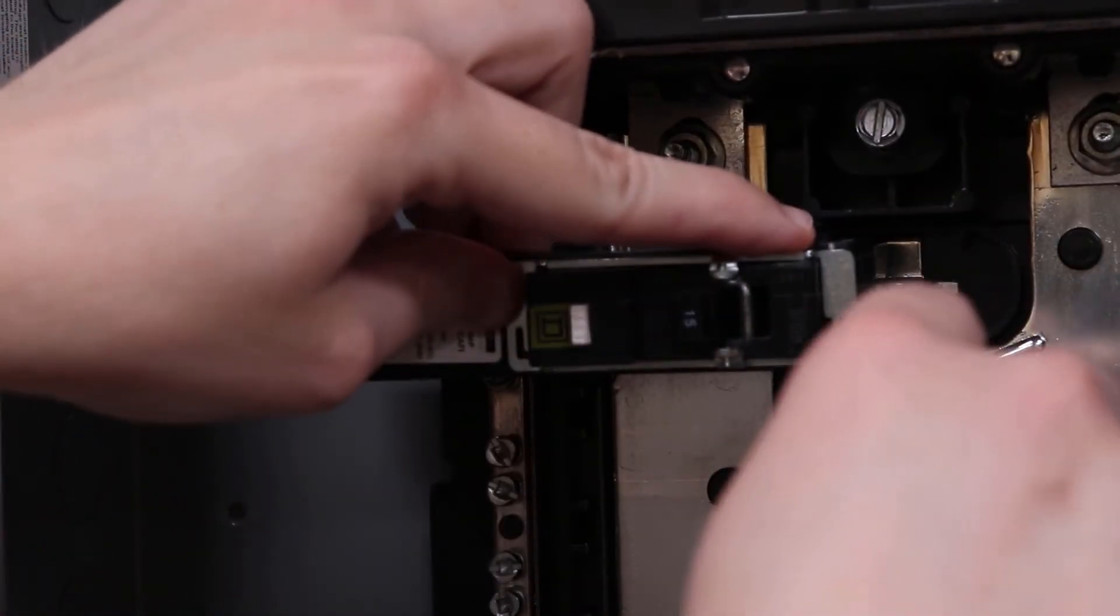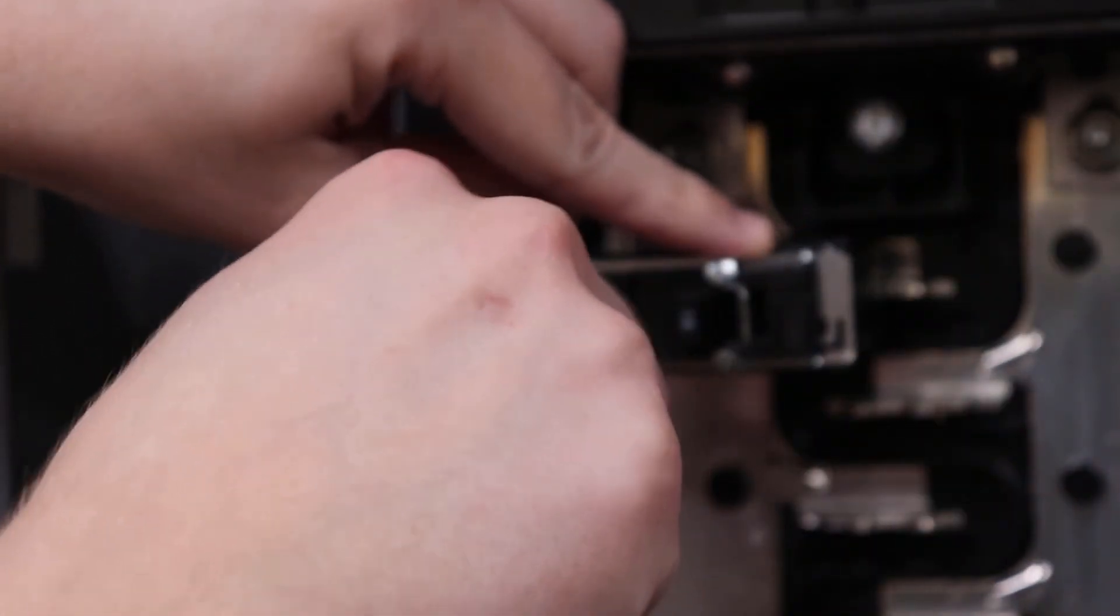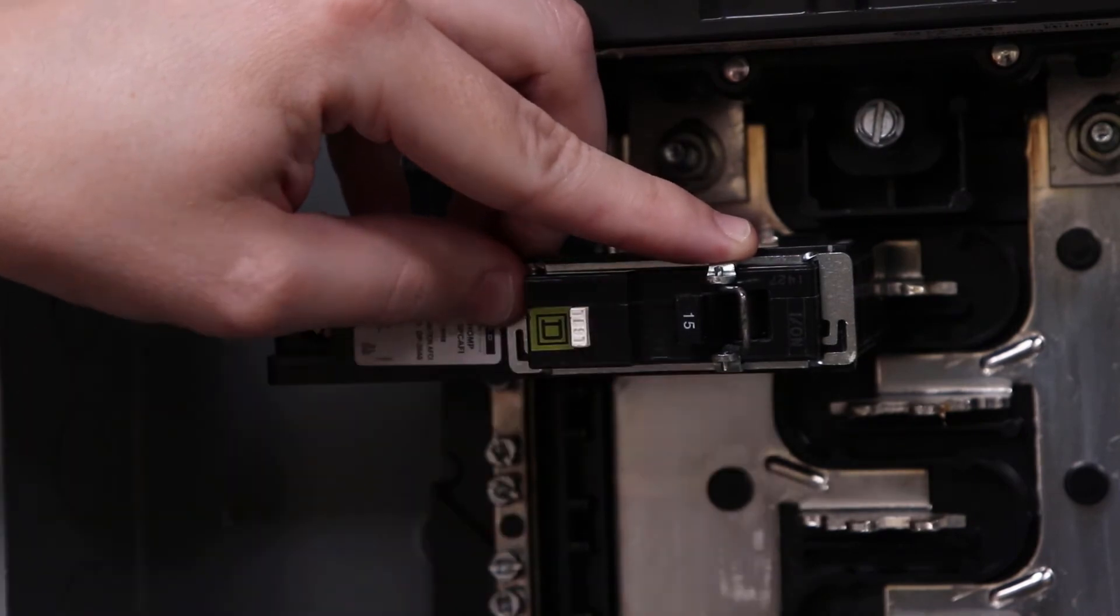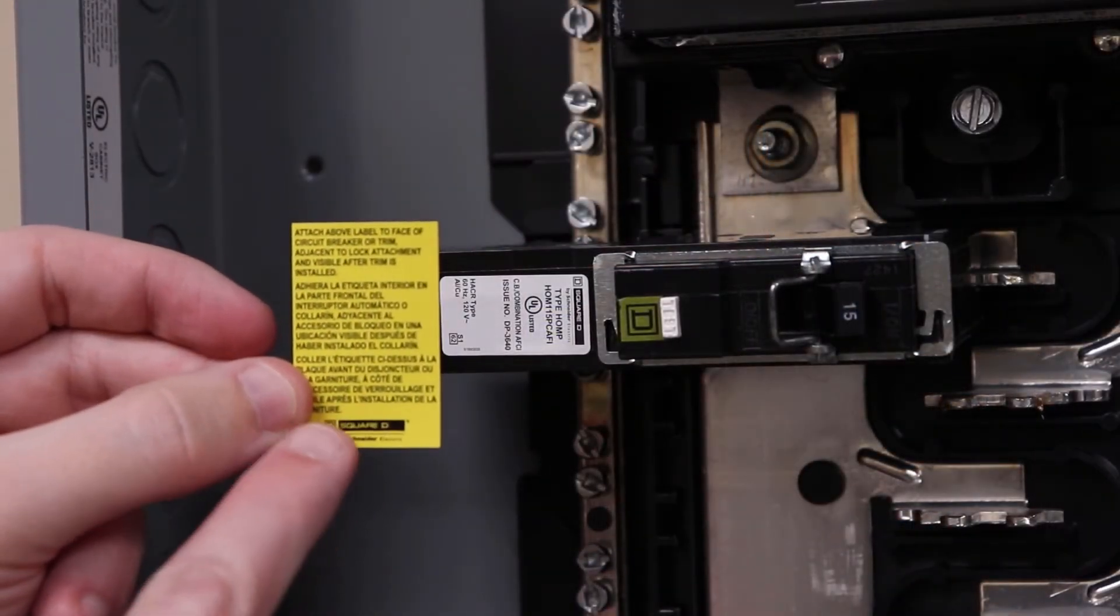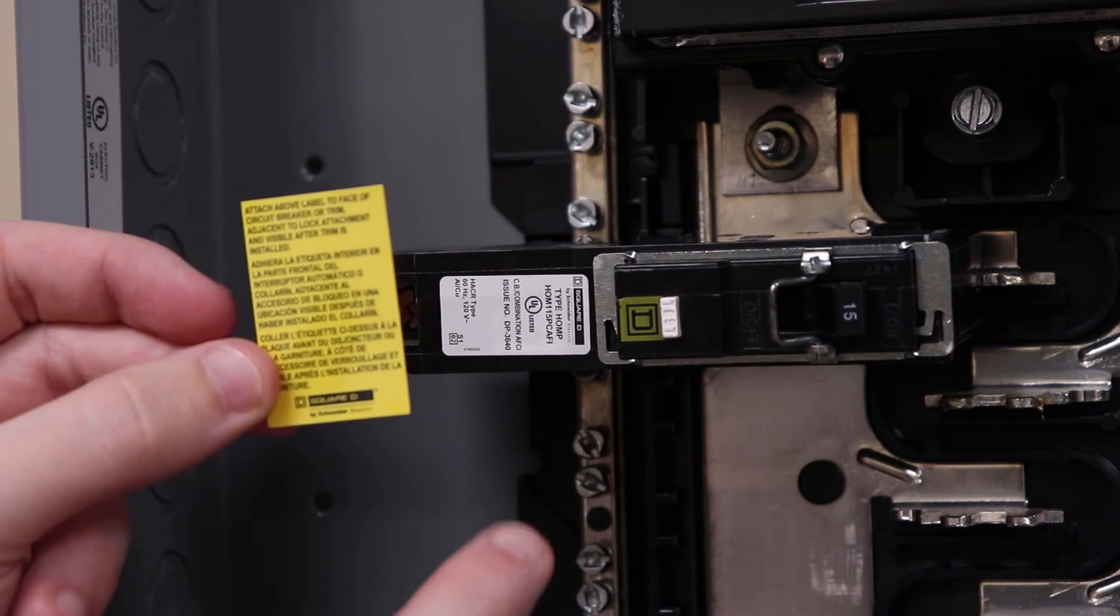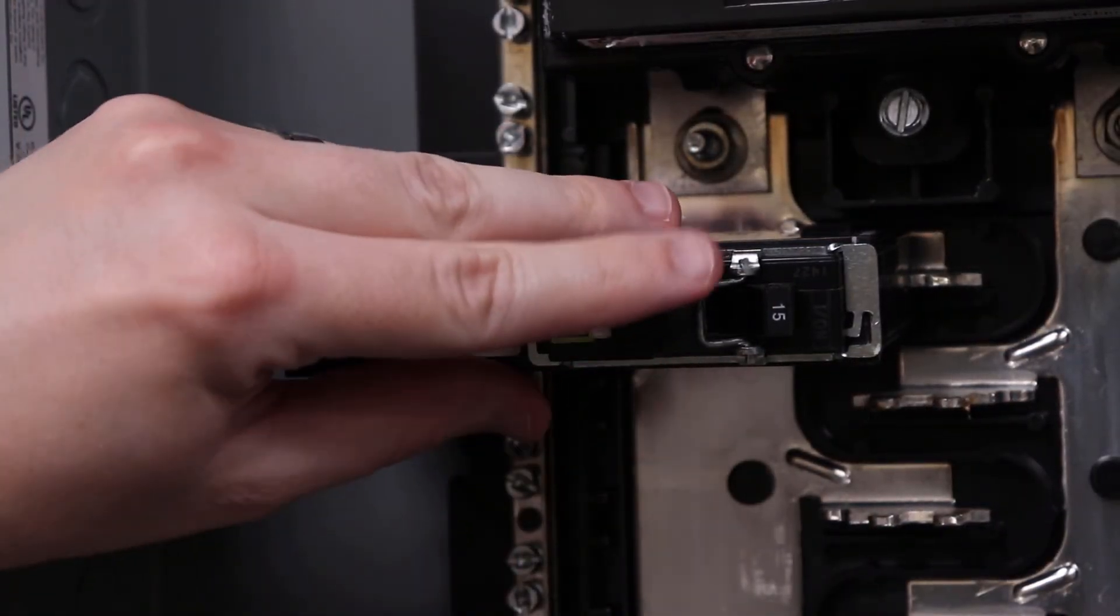Use a screwdriver to slide the locking tabs here and here into the slots on the breaker. Make sure to attach the label to either the face of the breaker or to the cover. You can now lock the circuit breaker in either the on or off position.